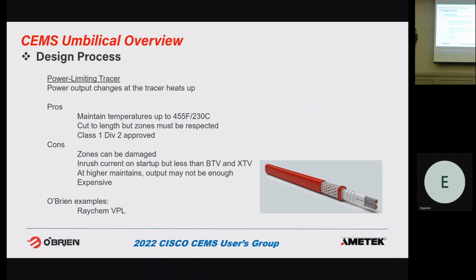Why that's important is when you're putting a tubing bundle in and you're using a zone style tracer, you have to be concerned at the very ends where you're cutting that tracer, only complete zones make heat. So if you're cutting the tracer, in between each zone is called a node. From that point till that next node, it's not producing heat. So you want to make sure when you're cutting your bundle, you have extra tracer coming out, so you know that the tubing bundle or that process is heated all the way to the end of the bundle and then outside of it.